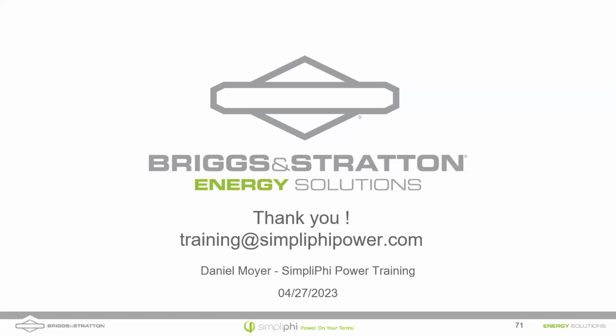Could you touch again on the amount of cycles and the depth of discharge these batteries can handle? This was an anonymous question, and I'll answer it here. If you limit depth of discharge to 80%, leaving 20% of the energy in the battery each cycle, we expect you to get 10,000 cycles, and we warranty it no matter what for 10 years. Cycling once daily, that's about 27 years.